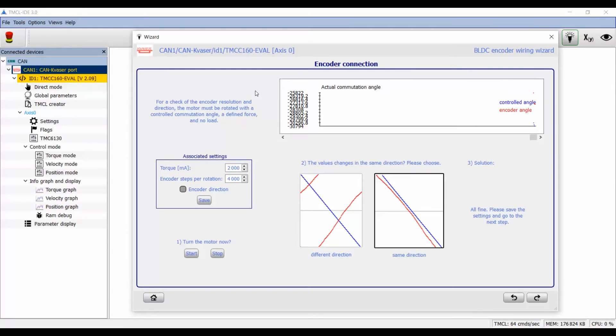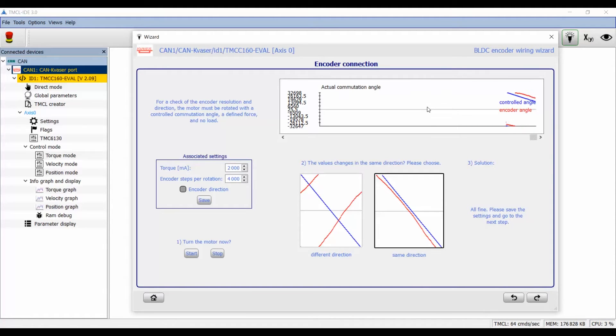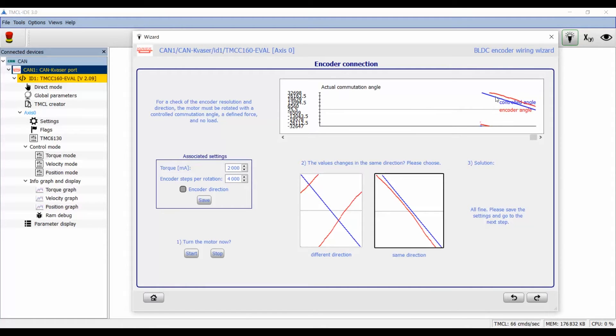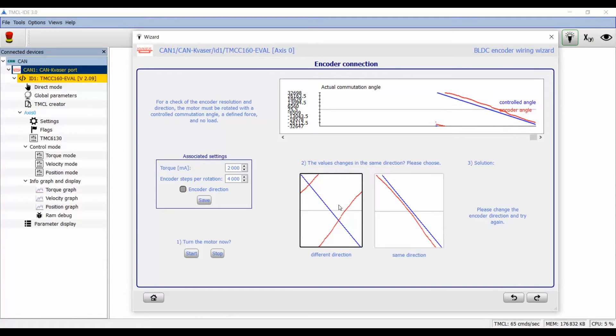The wizard uses the open loop mode to rotate the motor slowly with a constant torque. We can select this torque here and start the motor. Afterwards we take a look at the actual commutation angle used for the open loop mode. This is the blue line and we compare it with the commutation angle computed by the actual encoder signals. This is the red line.